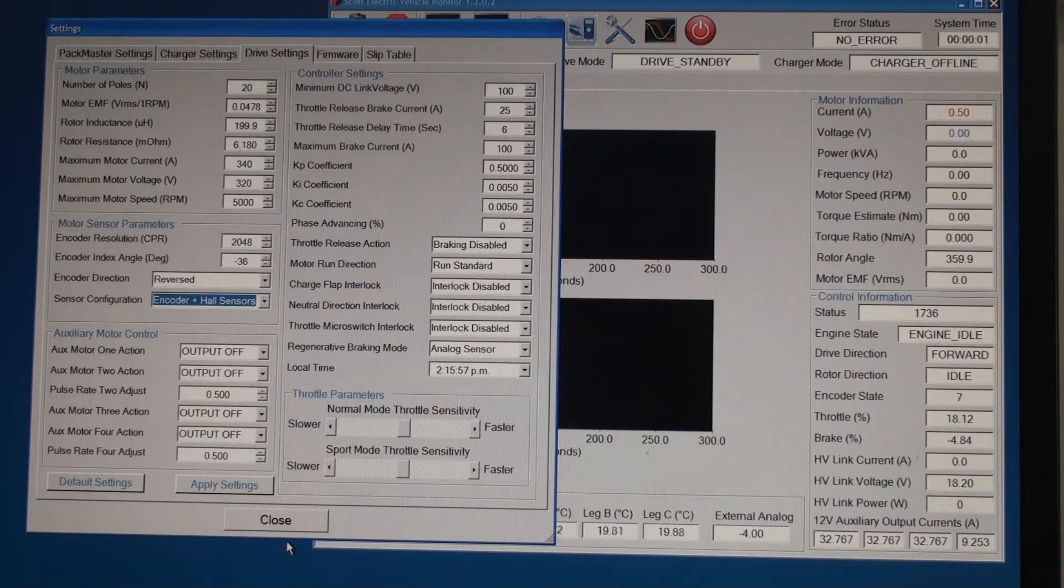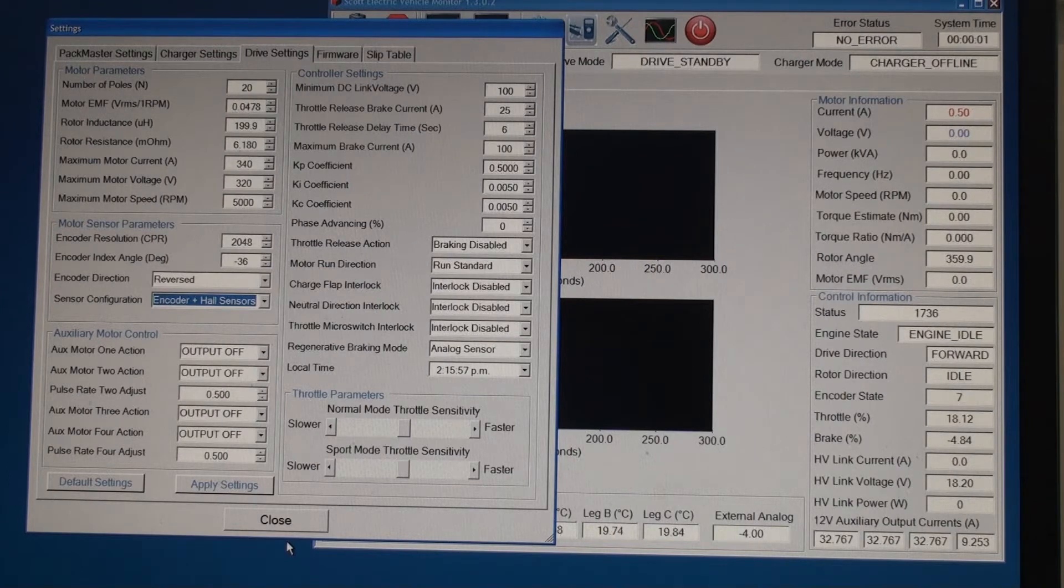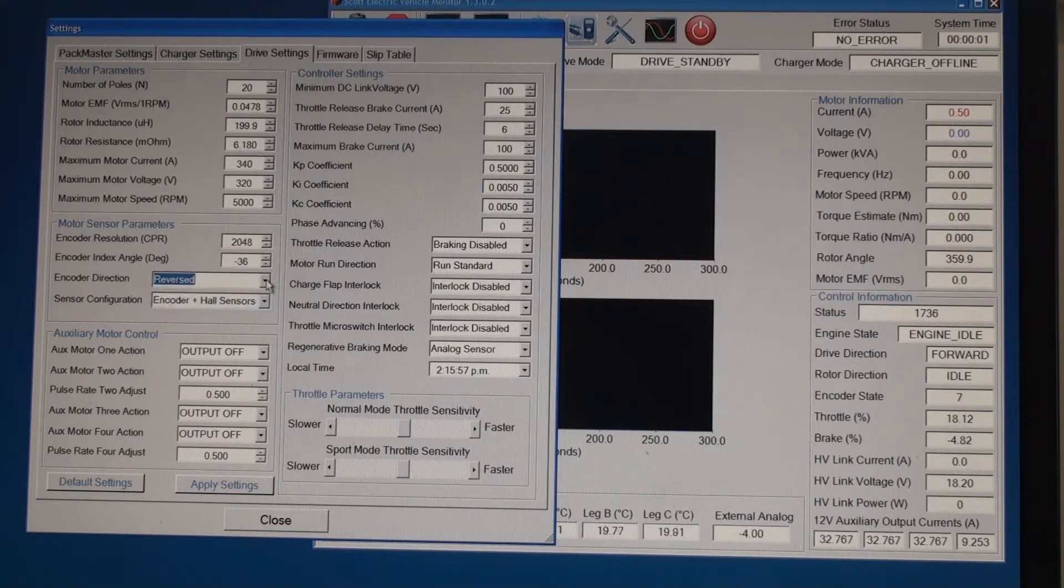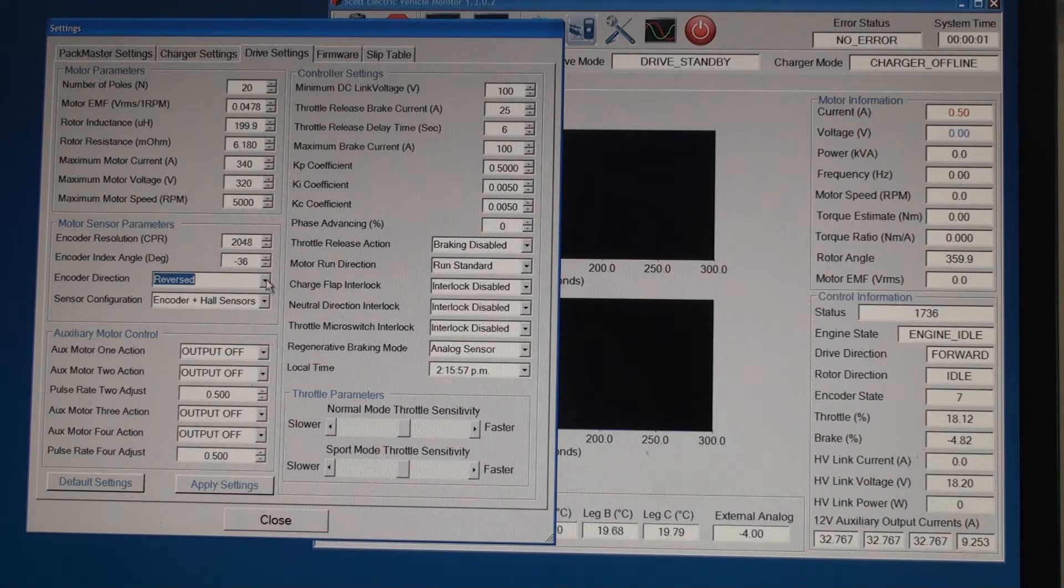The next setting we need to enter is encoder direction. For this encoder and motor we needed to set it to reversed. The other option is standard. If we set it to standard on this option then the rotor locks when we try to run it. So the correct setting is reversed.